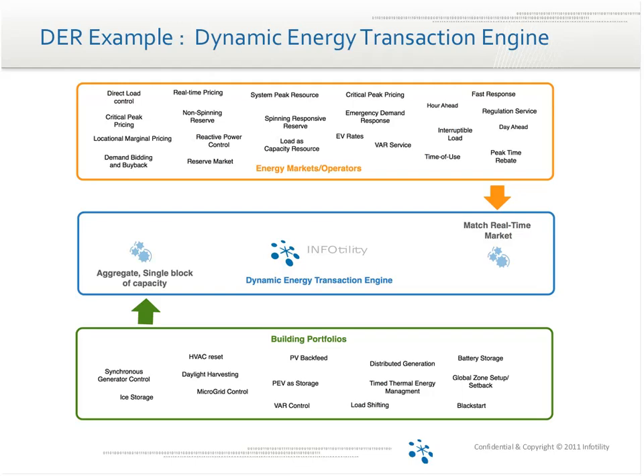So distributed energy resources, even things like demand response—we're working on a project where you aggregate multiple buildings, measuring it in very fast increments. Lawrence Berkeley Lab has done lots of work on this, but we're doing a test pilot with New York ISO and Con Edison territory, where you aggregate multiple buildings to get a minimum of a megawatt available, then within 10 minutes ramp it up, and do 6-second telemetry to verify you're doing it. From the grid's perspective, that looks like an ancillary service.